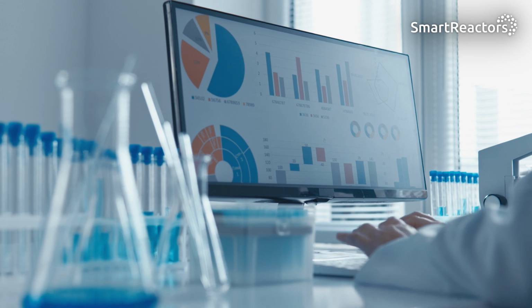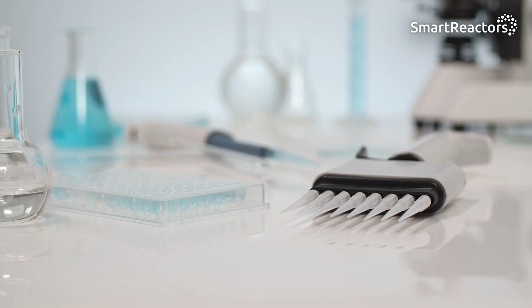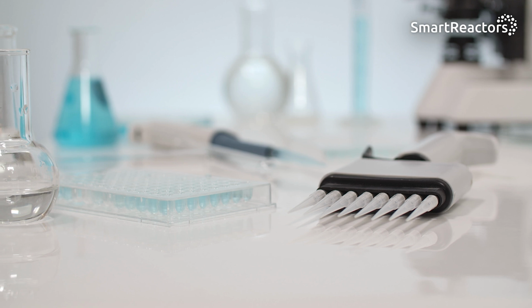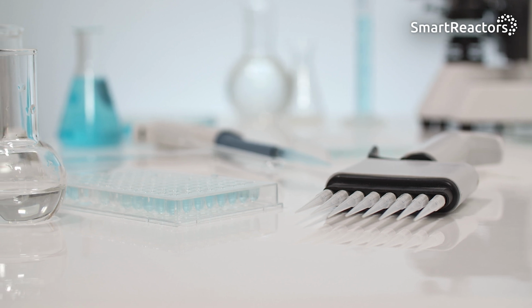When you're picking a coating, it's important that you have biocompatibility data. There are a lot of coatings that have early proof of concept work. These tend to come out of universities, but they often lack the ISO 10993 biocompatibility data that you're going to need to gain regulatory approval for your device with the coating. So when you're selecting a supplier, it is important that you make sure they have that biocompatibility data on file. It's also very important to ensure that all reagents, all consumables, everything that comes in contact with that chemical process is of an appropriate grade and that there is a robust supply chain.